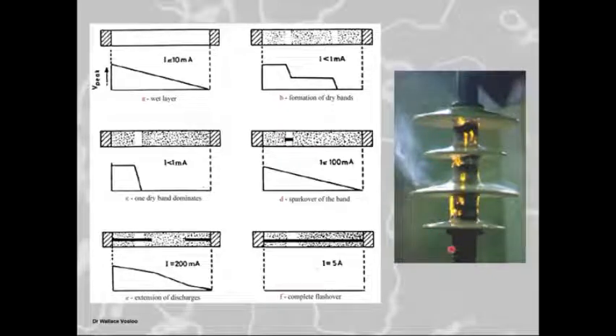So once you've got the conducting pollution layer on the surface, the current starts flowing. It doesn't just flow over one side, it flows around the whole insulator and across the surface over the whole insulator, right? Now, where's the current density the highest? The current density is the highest around this rod sheath section here in the center. When you've got 500 milliamps flowing there, it's distributed over a large surface, so you're not getting localized heating, okay? When it flows through a narrower, smaller surface area, your joule heating is higher. And it doesn't just heat on one side, it heats right around.